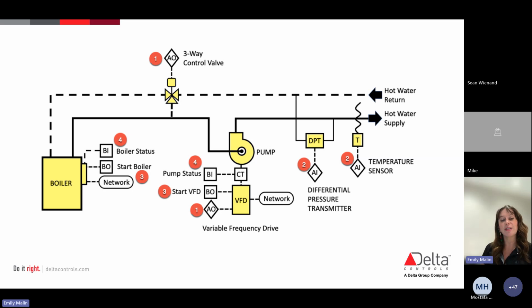A couple of the different outputs that you'll see on here are your burner control and your pump control. And we see on here our boiler. We have our boiler status and our start boiler as two of our inputs and outputs. Again, that B in front just means that it's binary. So that's binary or digital, right? Those two words mean the same thing. Moose took us through that. You're all pros at that by now. But basically, this is just saying we need to be monitoring whether or not our boiler status is on or off, and we need to have an output there for whether or not we need to start the boiler.